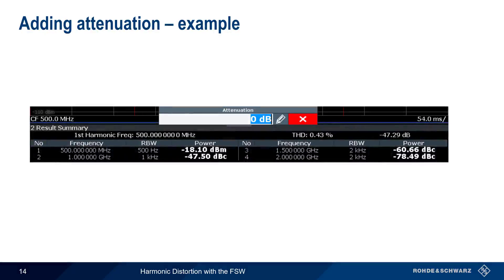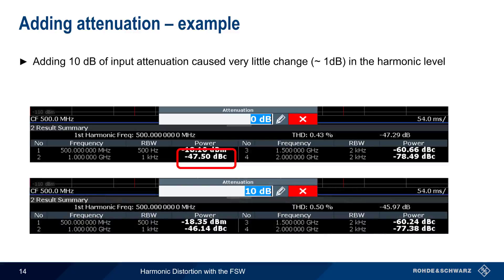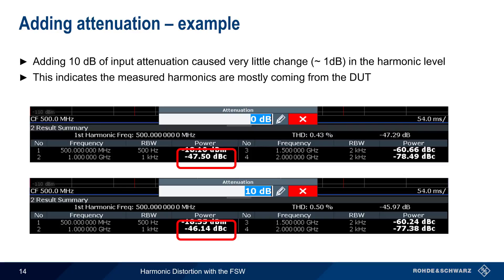Let's look at an example. Here are the levels of the harmonics without additional attenuation. Note, in particular, the level of the second harmonic: minus 47.5 dBc. When 10 dB of attenuation is added, the level of the second harmonic changes by less than 1 dB, to minus 46.14 dBc. So in this case, we can say that the analyzer is adding little to no harmonic distortion to the measured signal.